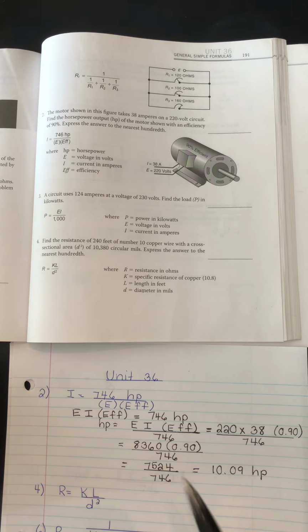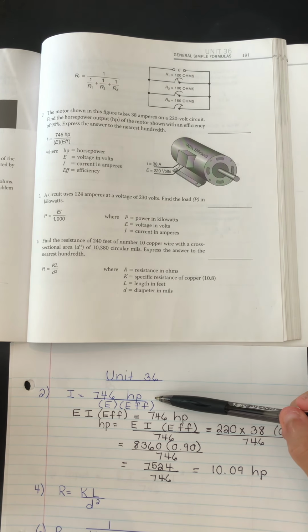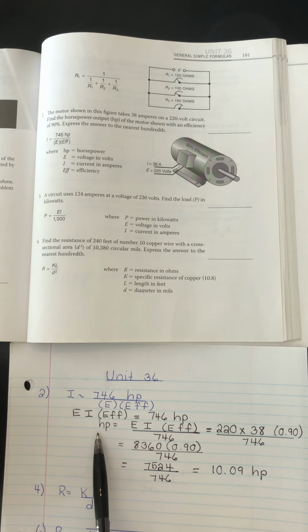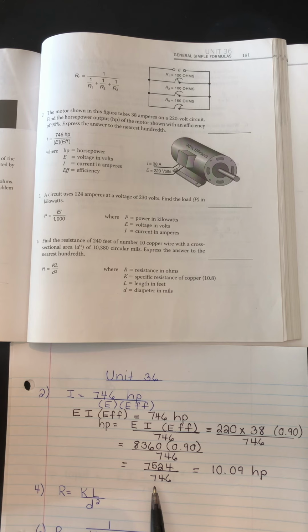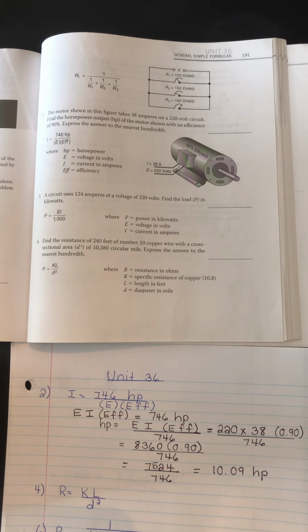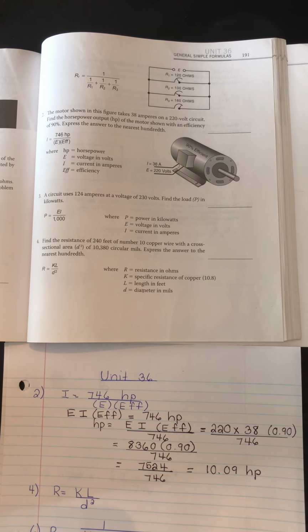Okay? So once again, we took the original equation and we isolated HP. Okay, when you multiply E by I, you get 8360 watts, which is the input power. After multiplying it by 0.9, you get 7524 watts, which is the output power. And then when you divide it by 746, you get that same output power, but in the unit horsepower. And we're dividing by 746 because every one horsepower is equal to 746 watts. And this is something we reviewed in a previous lesson.